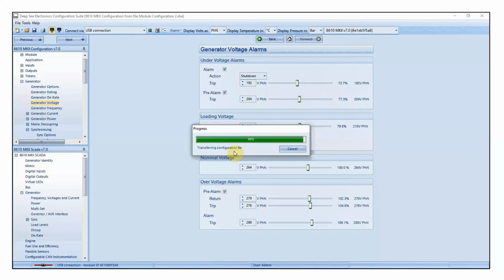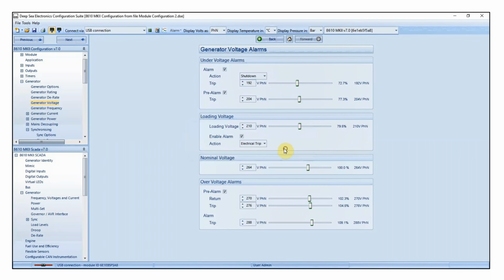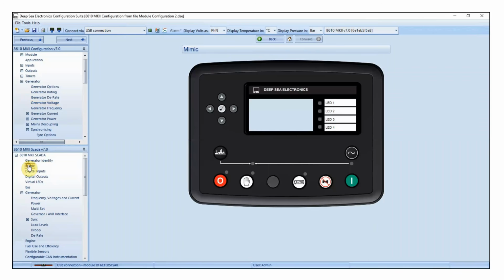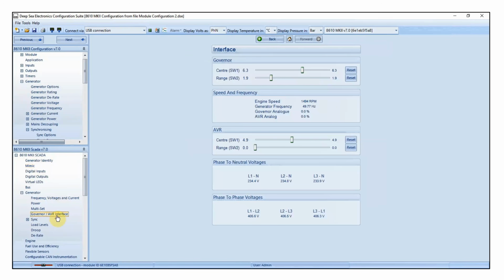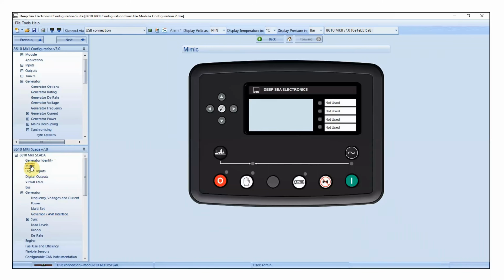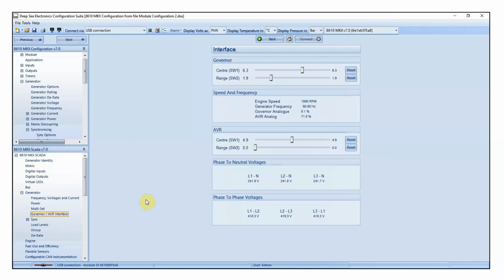Just like before with the governor setup, we're going to increase the nominal voltage to 264, 10%. We're then going to start the generator with the generator breaker open. The generator will still run at its nominal voltage. Then as soon as we close the generator breaker, you will see the voltage start to increase to that new nominal voltage, in my example, 264. So here we are starting the gen. You can see the breaker is open. We then go to the governor and AVR interface, and you can see the nominal voltage is still 240. Once we close the breaker, you'll see this time the voltage has correctly increased.